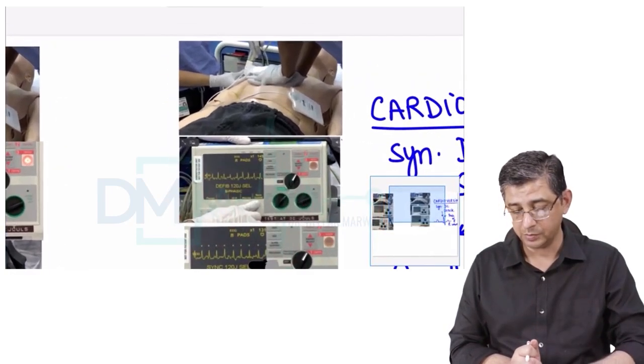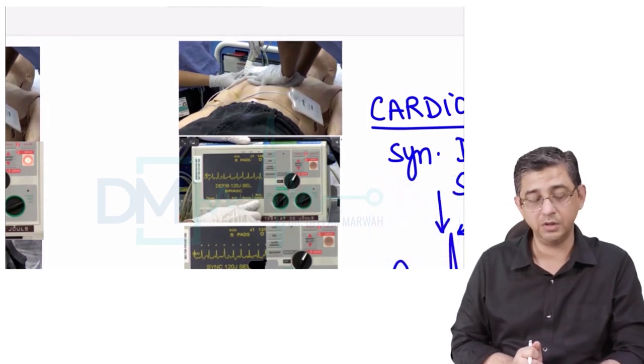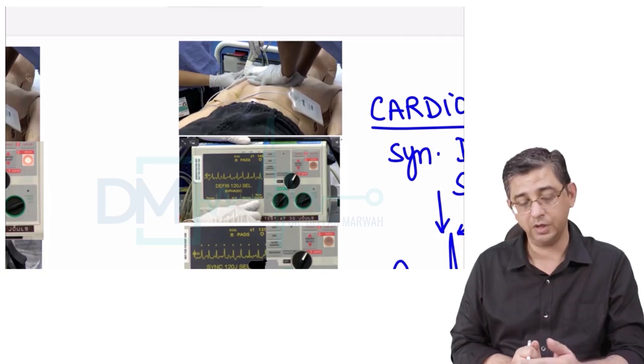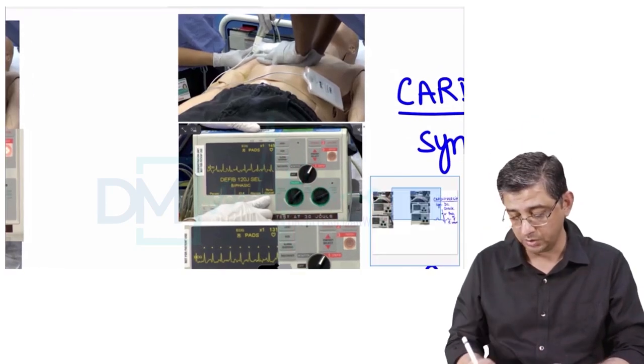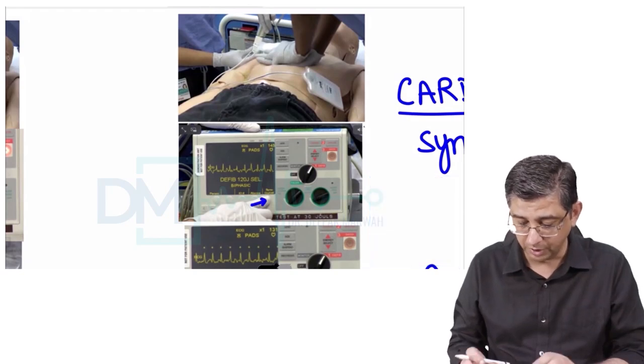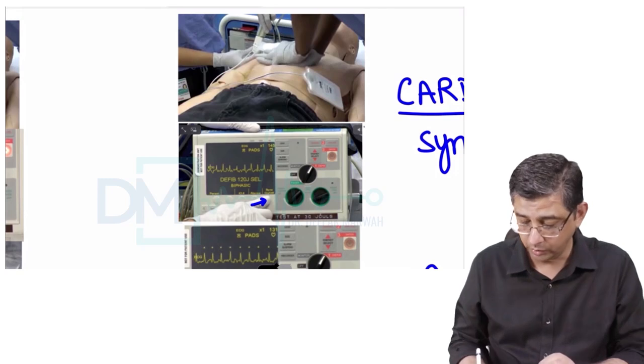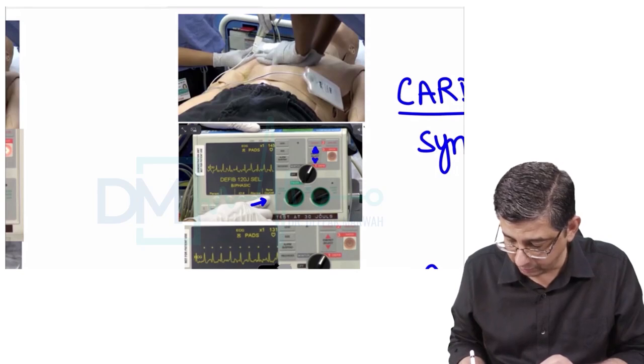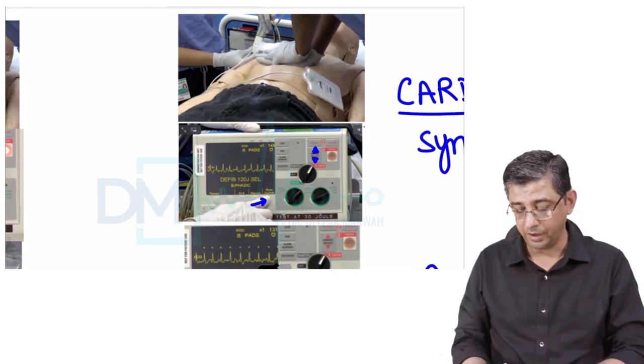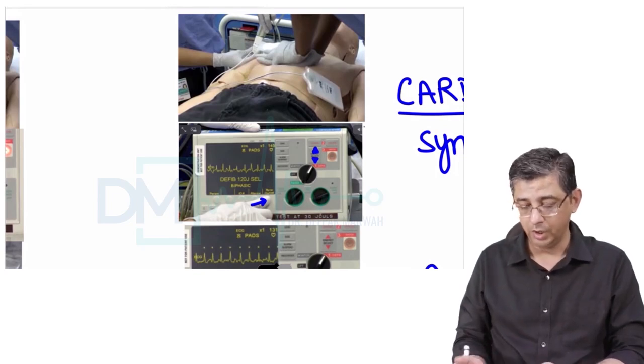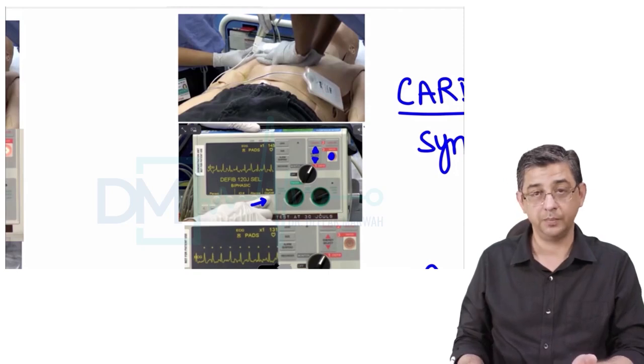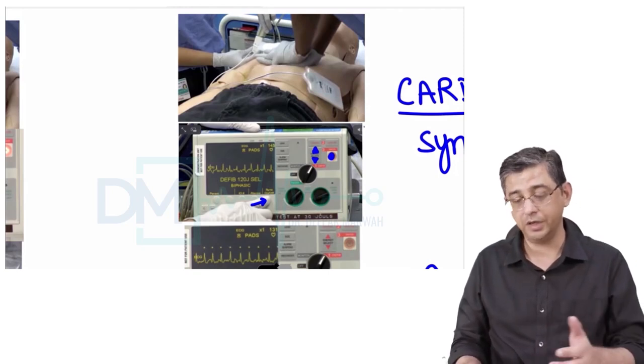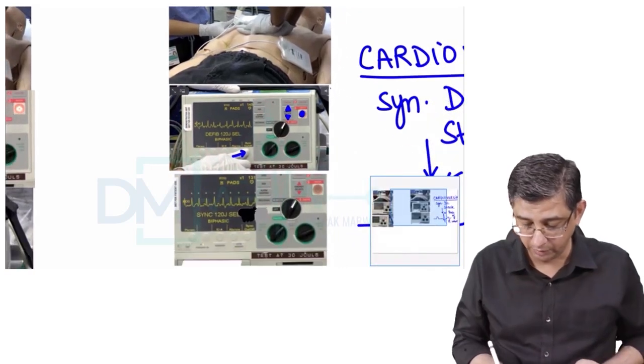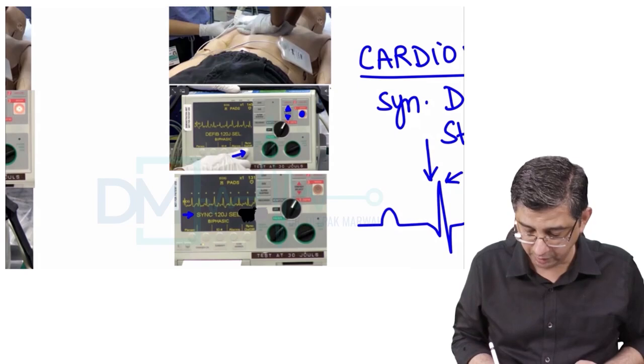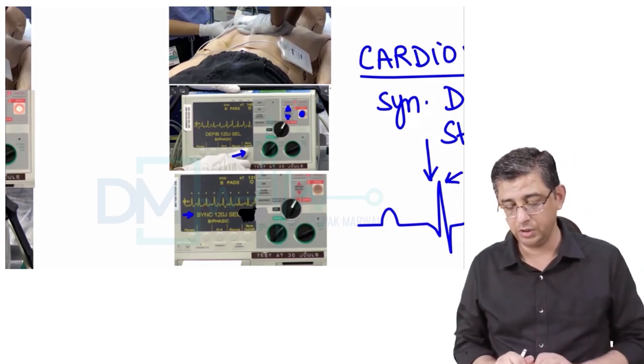For example, in this image, you can see the hands of the doctor giving CPR and the paddles have been put on the chest by his colleague. Now you can notice a doctor pressing a button which will deliver a synchronized DC shock. You can adjust the power, increase or decrease the intensity of the DC shock by this display button here. Once you've set the value, you press this button and say shocking. When you say shocking, everybody will stay clear of the patient, and the computer will deliver. You can see on the display it will be written synchronized biphasic 120 joules delivered to the patient.